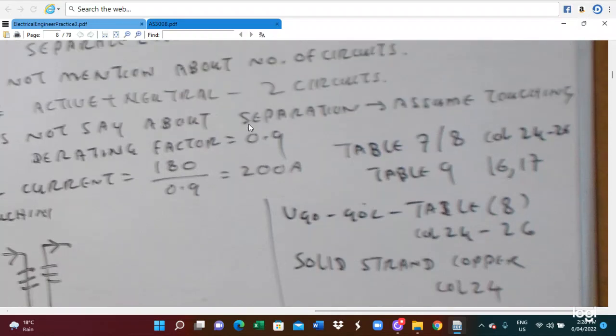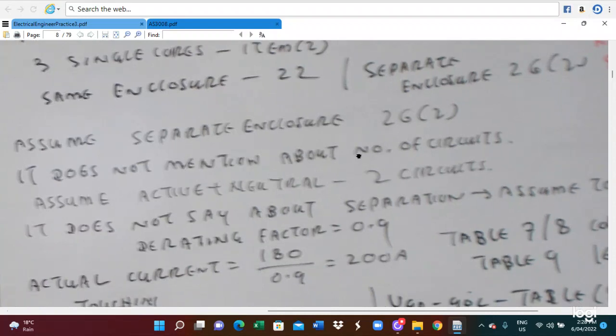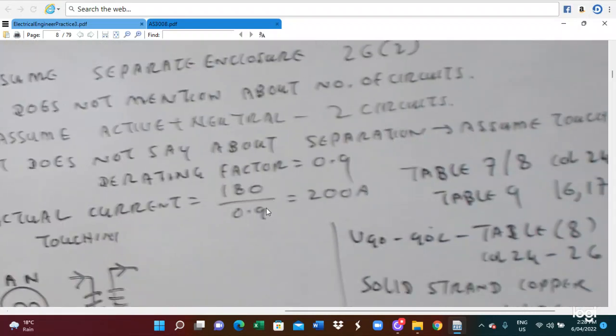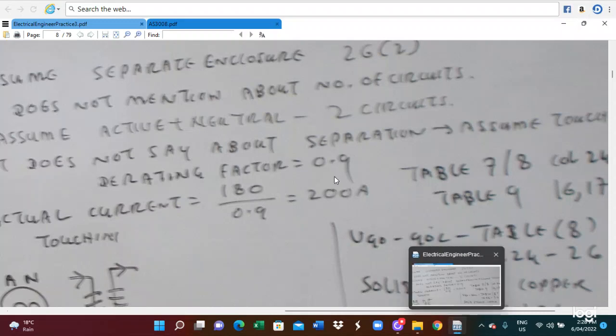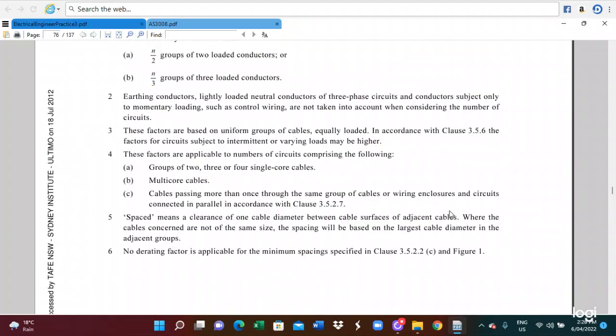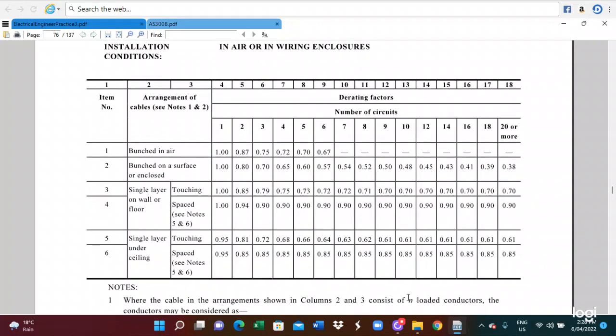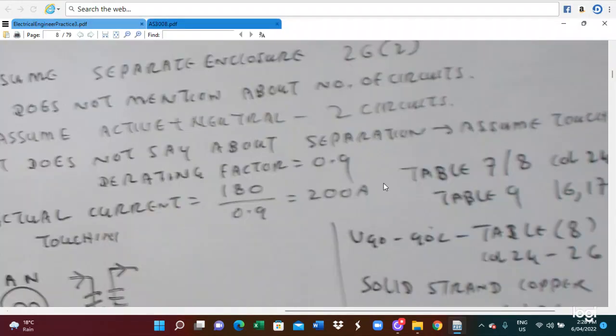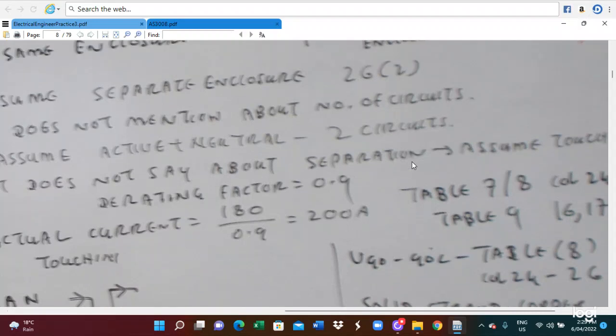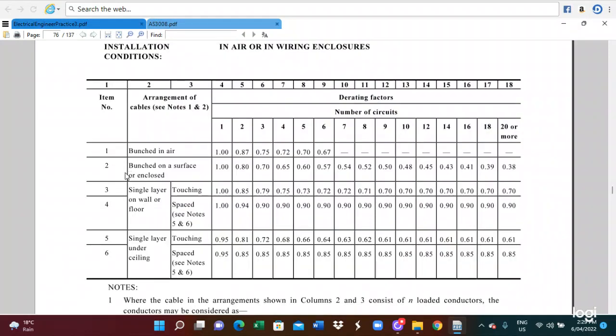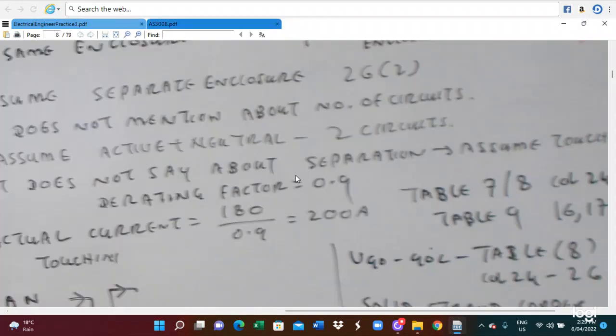In this case, the maximum demand current is already given as 180 ampere. We have to find the derating factor first, and based on the derating factor we look at table 8. So we need to find the derating factor from table 22. This is table 22. How many circuits? There will be 2 circuits, because active and neutral make 2 circuits. So the number of derating circuits is 2. Also we have to select the item.